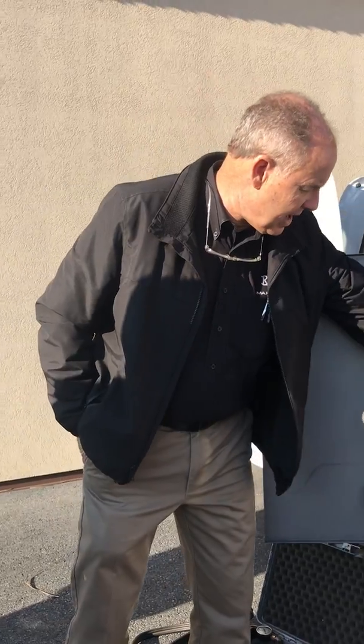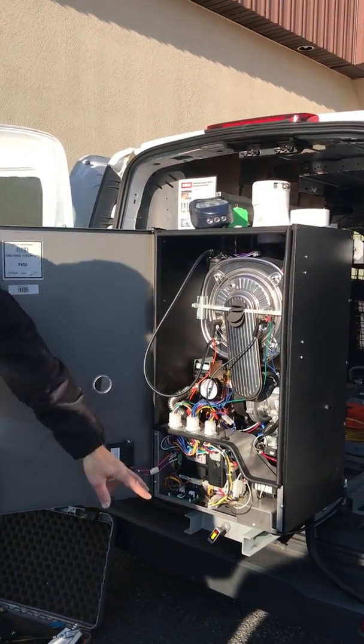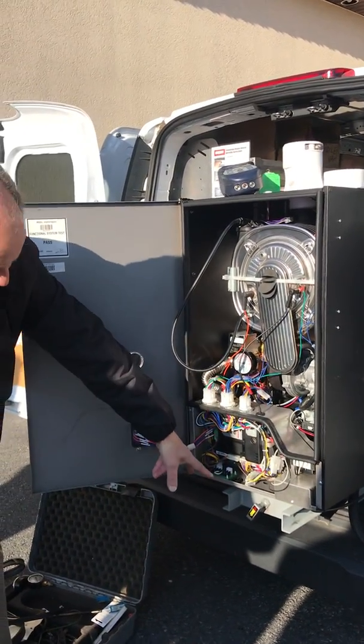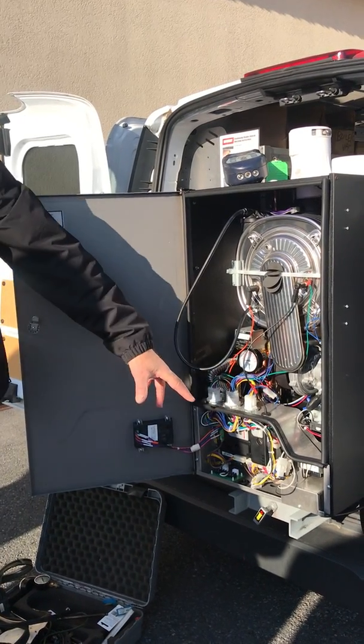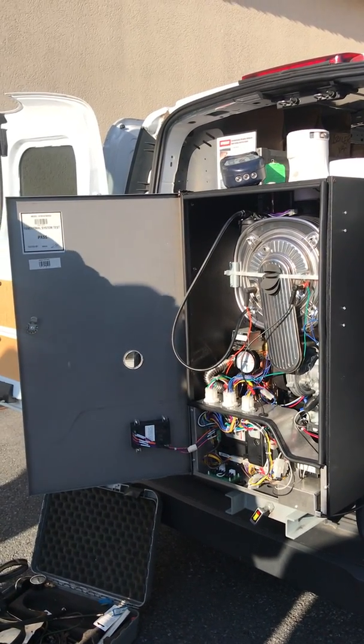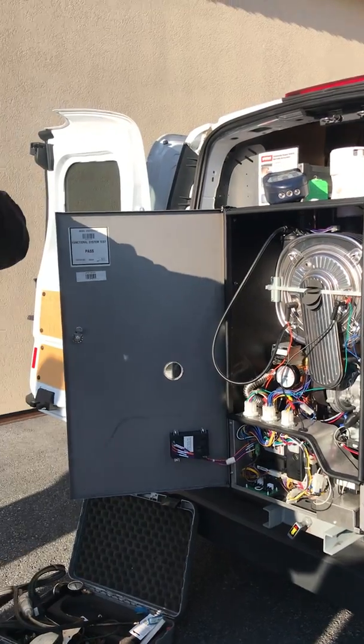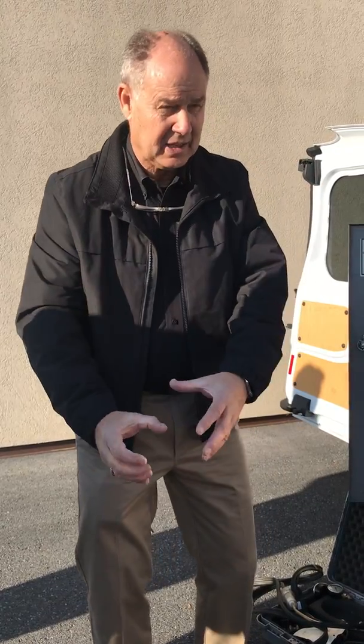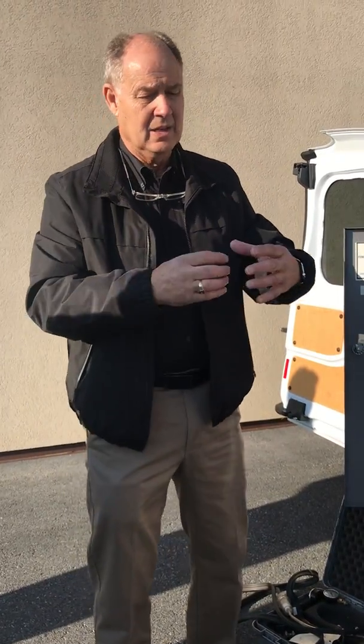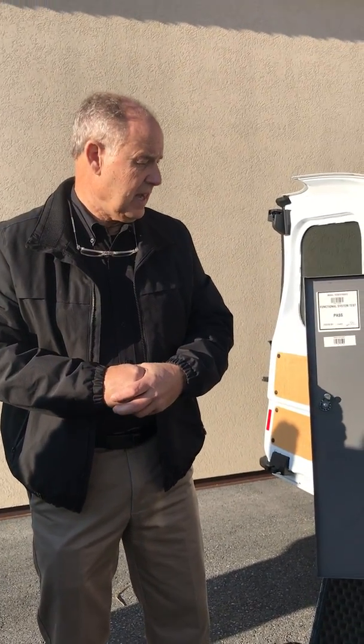This is your 3-way valve in here, and you have 2 domestic connections on the other side, my 2 space heating connections. The condensate that comes out of here, you don't seal it directly tight. It's going to be like 1.25 inch pipe that's going to come down, we'll run our hose into there. It's not sealed up tight. Can go down to the condensate pump or go down to a drain, but it's not totally tight. It has an air break in there. So when we're doing that.